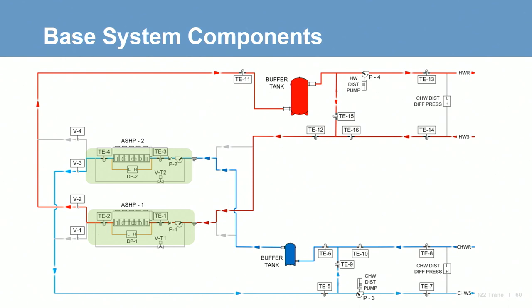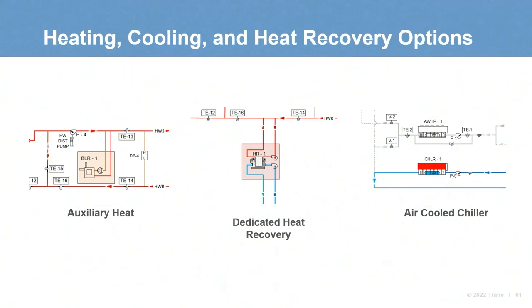Last pieces are our primary or production pumps. Typically, each unit would have its own dedicated pump. These pumps can be constant or variable speed. For simplicity and due to the often lack of unit turndown, pumps are typically selected with VFDs and balanced to the specific heating and cooling design flow rates. Note that cooling and heating design flow rates are usually not the same, so drives are used to maintain high efficiency pumping. There are several options for the chiller heater system.